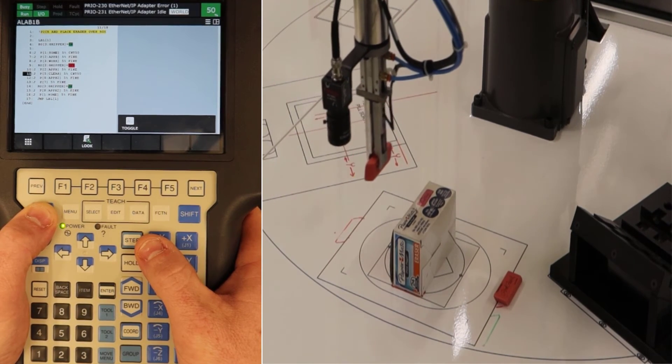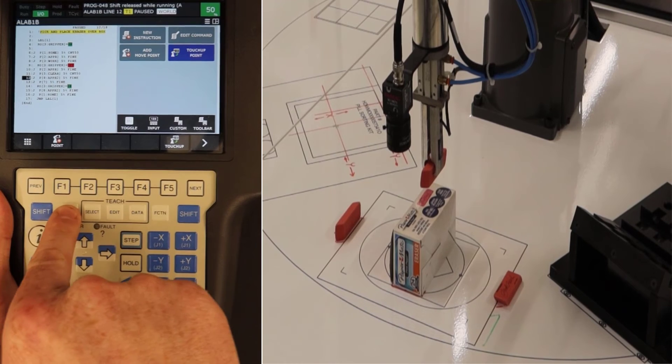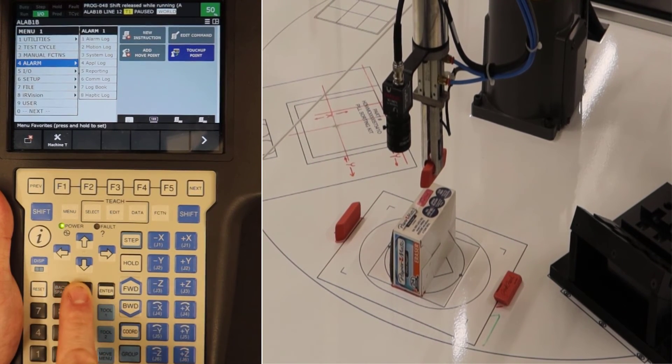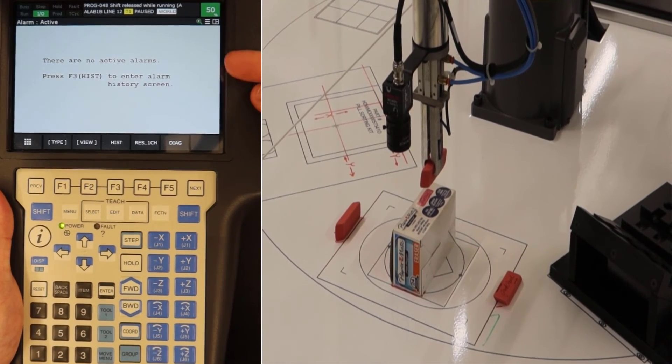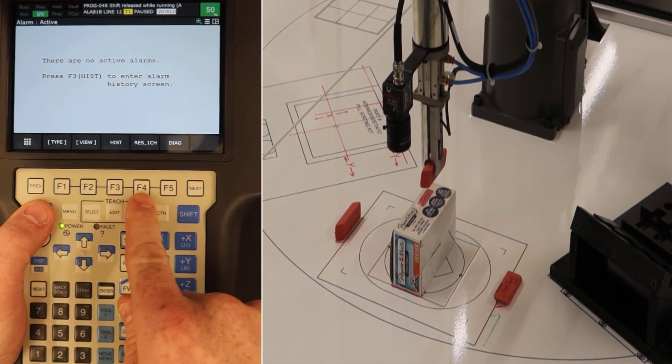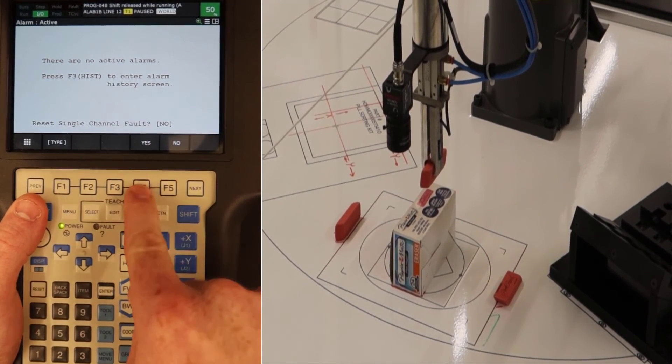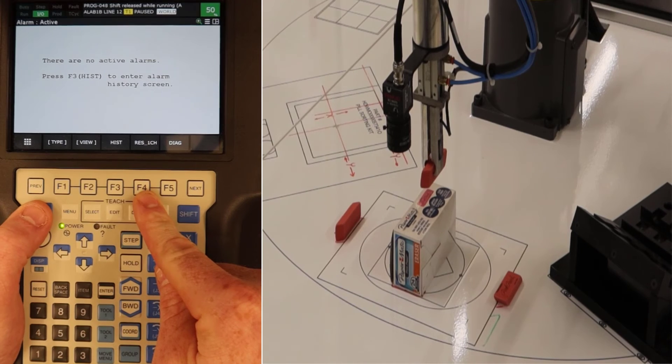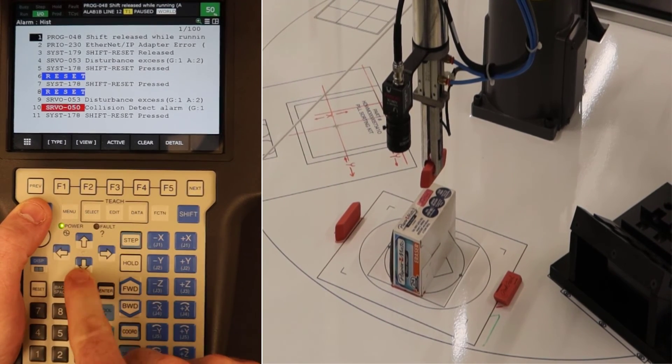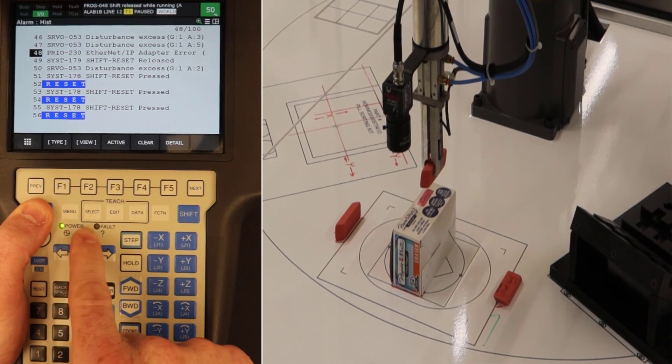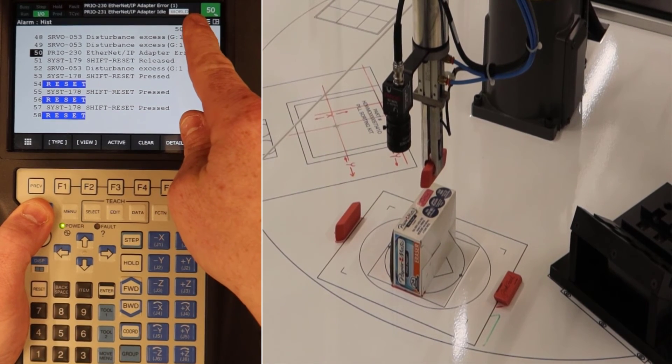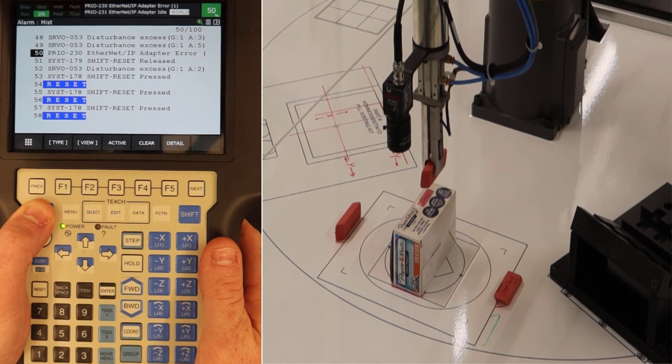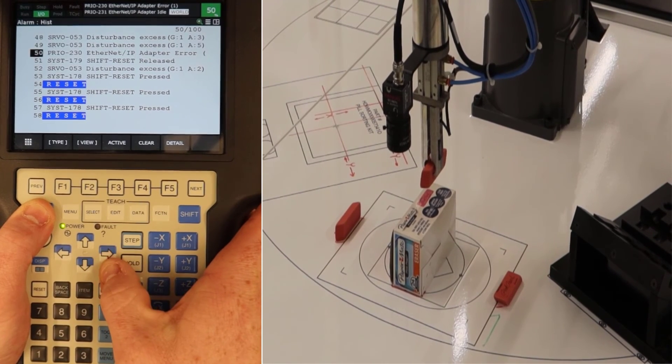Now the last thing I'll show you in terms of fault recovery and alarms is you can go into menu and scroll down to alarm. If you just hit enter, you'll see an alarm log. And this will actually actively tell you there are no active alarms. Sometimes there will be a pulse encoder alarm, and the easiest thing to do with that is to hold down reset the single channel fault. And basically what that does is it clears all of the alarms from each servo axis. So you can also go back and look at history and page down and see the different errors. We've had a lot of disturbances today. We also have an ongoing error that says ethernet IP adapter error. It's not a fault, it's just telling us that we have not yet set up our ethernet communication access. So that should be something that's just regarded as normal if it's not needed.